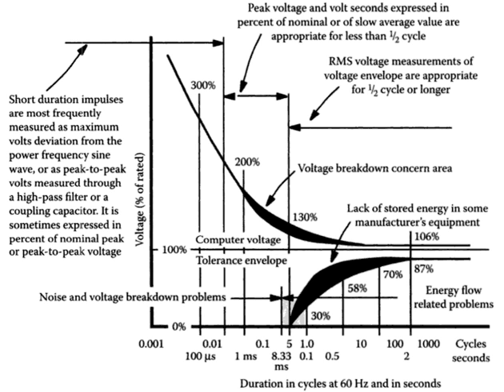Topic: Voltage. Variations in the peak or RMS voltage are both important to different types of equipment. When the RMS voltage exceeds the nominal voltage by 10 to 80% for 0.5 cycle to 1 minute, the event is called a swell. A dip, in British English, or a sag in American English, the two terms are equivalent, is the opposite situation. The RMS voltage is below the nominal voltage by 10 to 90% for 0.5 cycle to 1 minute.